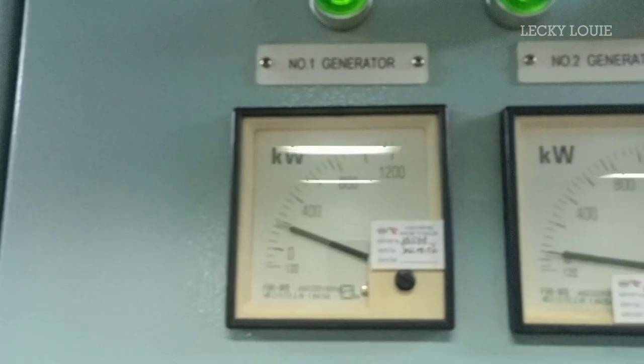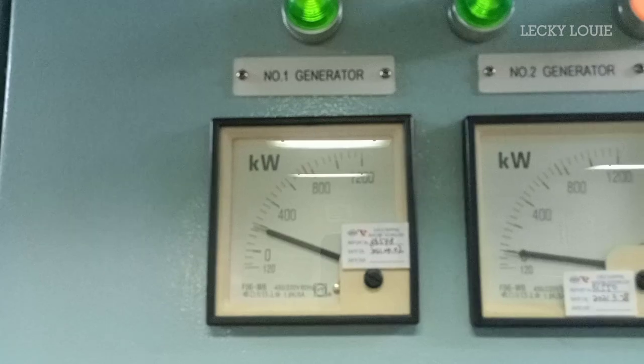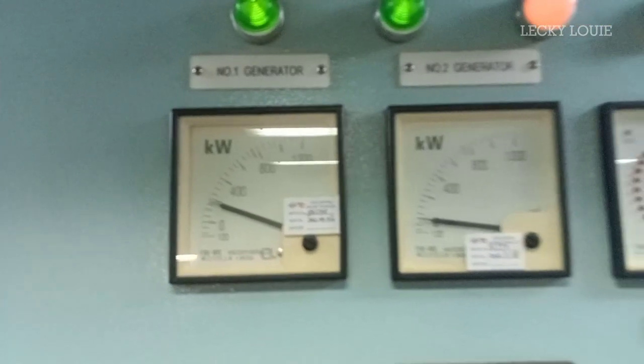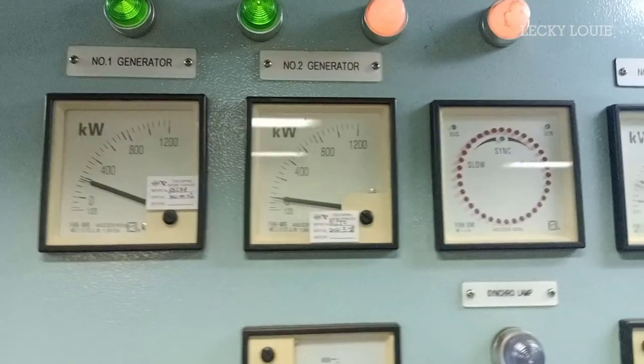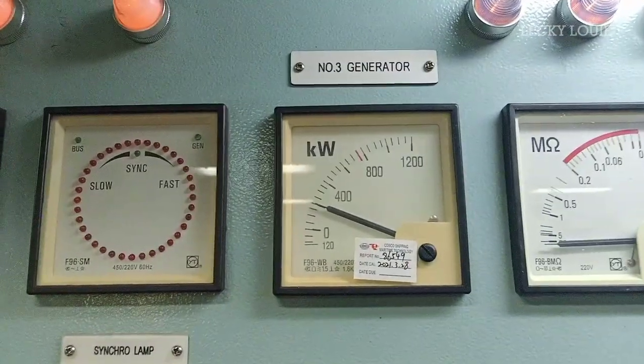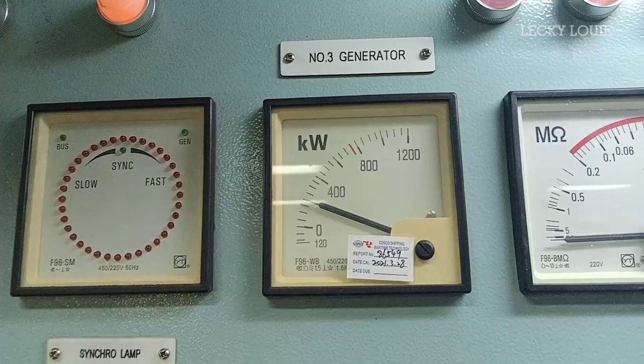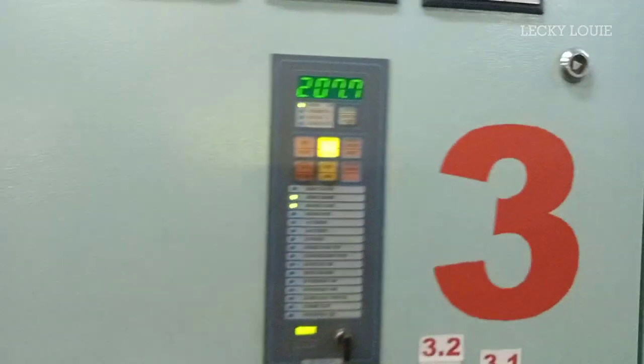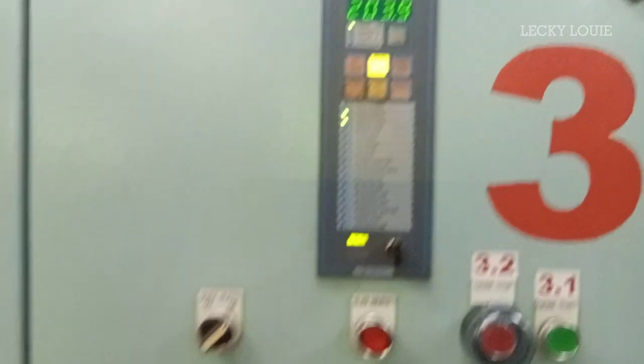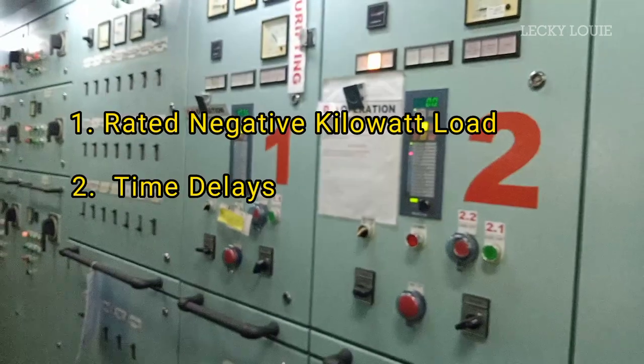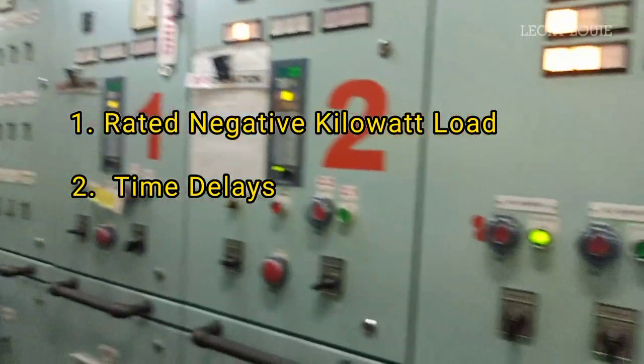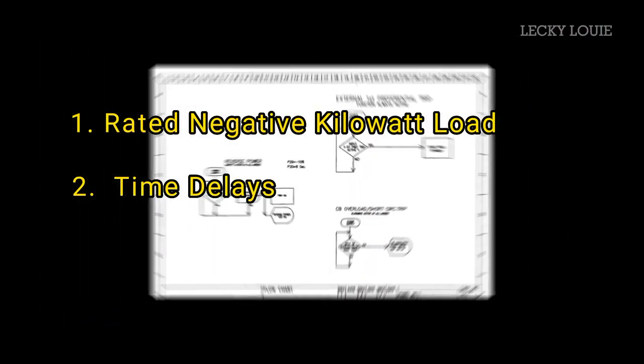Here in my company, it is included in our plant maintenance system to perform this reverse power test once every 3 months. To test the reverse power protection, 2 generators should be running in parallel and supplying the main switchboard. One generator is to be tested and the other one will remain in service. 2 factors govern the reverse power protection: the rated negative kilowatt load and the rated time delay.